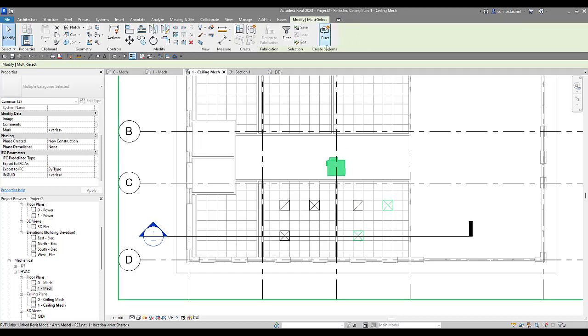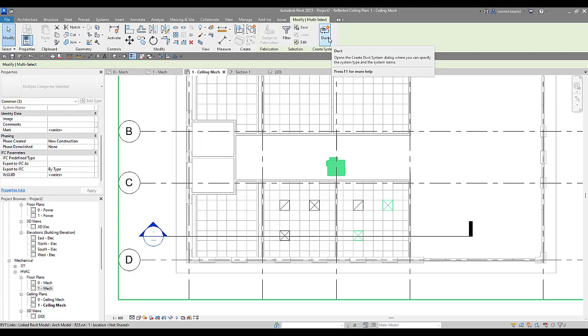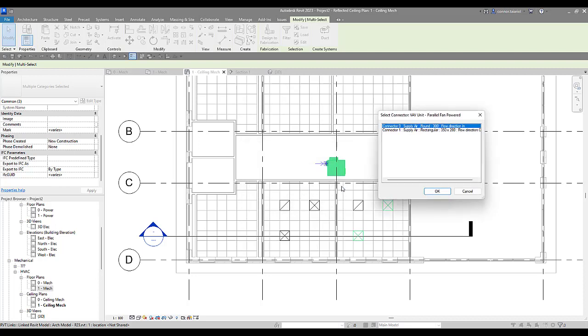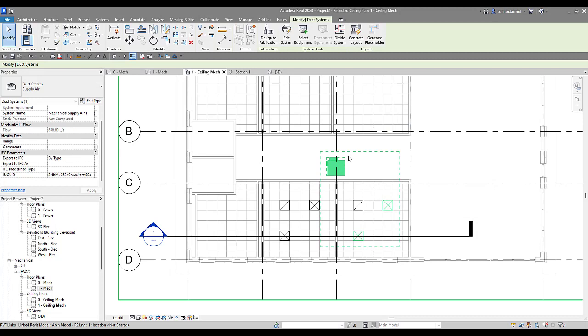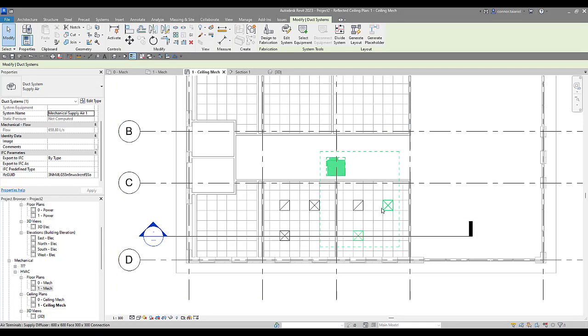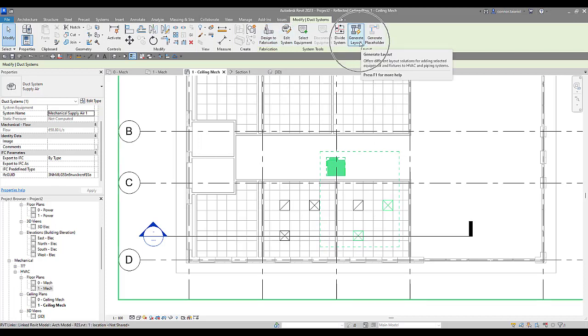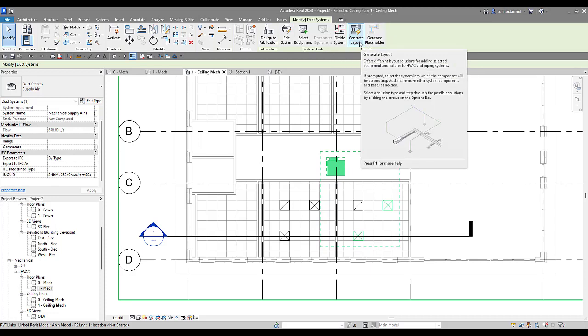Come up to the ribbon under modify, go to create system. We're going to create a duct system, mechanical system first. We're going to call it supply air. Grab the connector that you'd like. Press OK. And now you see a green dash box around everything that is highlighted, that is part of that system. Now back up in the ribbon under the modify tab, we can see that generate layout tool has now appeared. So we can now generate a layout and Revit will put in the ductwork for us.